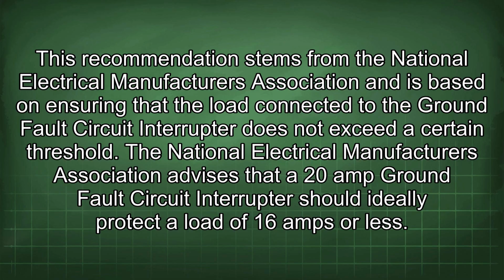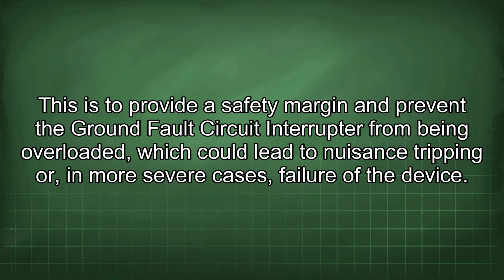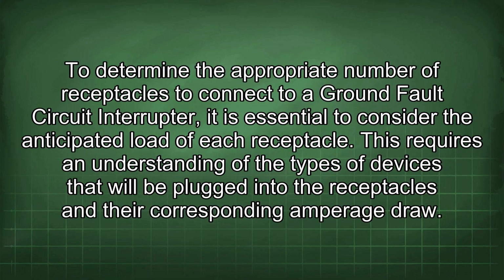The National Electrical Manufacturers Association advises that a 20-amp ground fault circuit interrupter should ideally protect a load of 16 amps or less. This is to provide a safety margin and prevent the ground fault circuit interrupter from being overloaded, which could lead to nuisance tripping or, in more severe cases, failure of the device. To determine the appropriate number of receptacles to connect to a ground fault circuit interrupter, it is essential to consider the anticipated load of each receptacle.